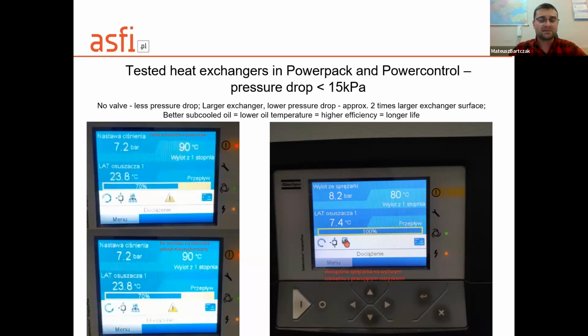So in this slide, I show 3 photos. In this one, we have a compressor without a heat exchanger. Our crew, our guys, always take a photo of the compressor controller before building in the heat exchanger. This picture under this first is the same compressor, and we caught the same moment of pressure and average load of the compressor. Here we have 70%, and here we have 70% too. The same pressure, the same temperature.